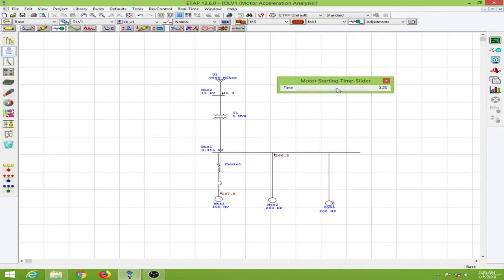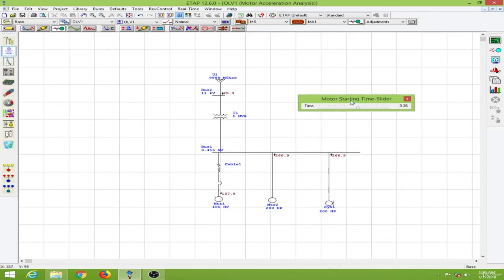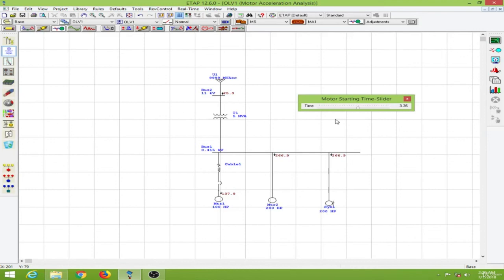So we can see the load current over here. And at 3 seconds the synchronous motor is also started over here. So we can see the load current here as well. So in static motor acceleration analysis what you see is the steady state currents over here. So you can't get the inrush moments and you can see the current reducing as the motor starts to pick up speed.